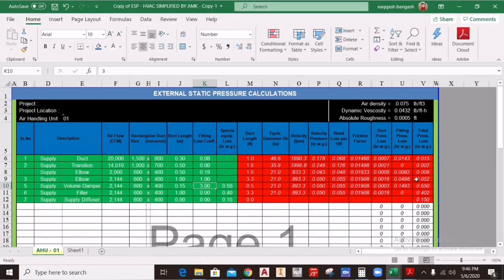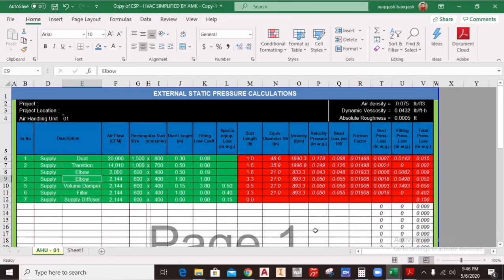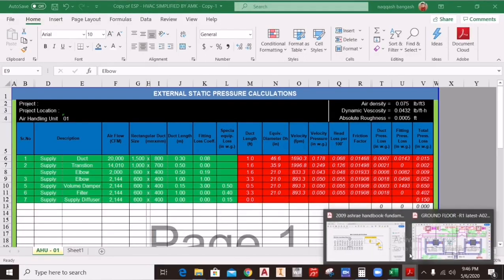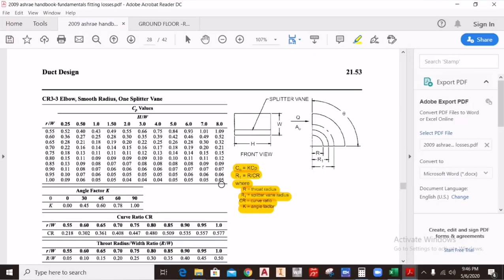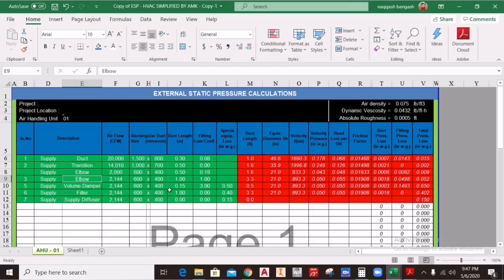For an elbow with vanes, the equation is the same: C0 = k × Cp. You also calculate Cp using h/w and r/w to get a value, then select your angle — for a 90-degree elbow with vanes, k = 1. Multiply k by Cp to get C0, and enter that value here. For example, C0 might be 0.15 for an elbow with vanes.